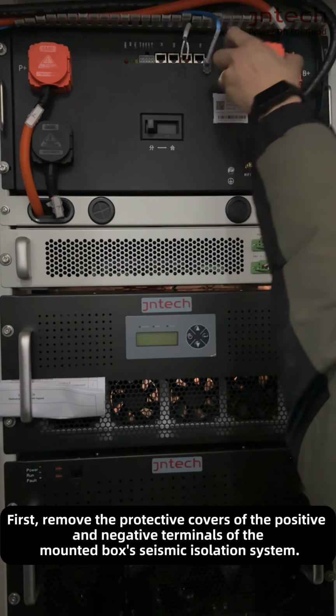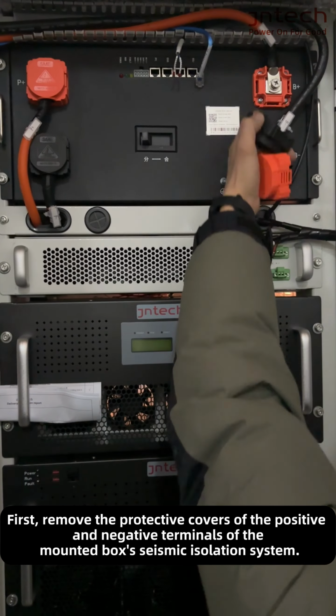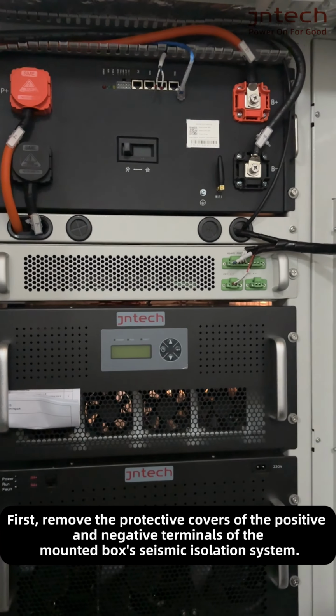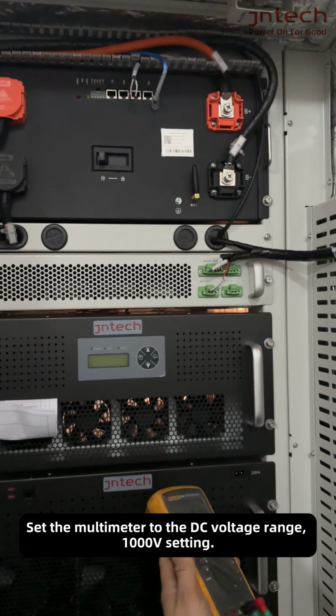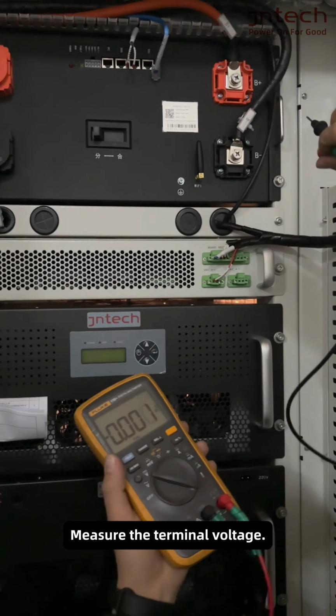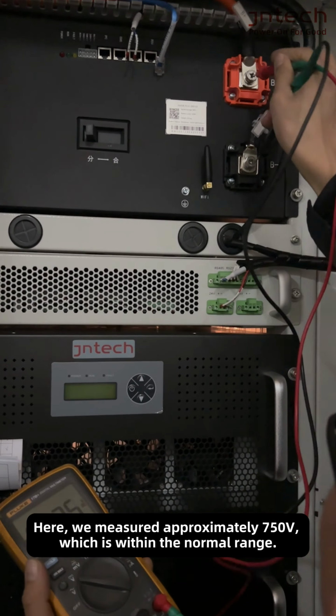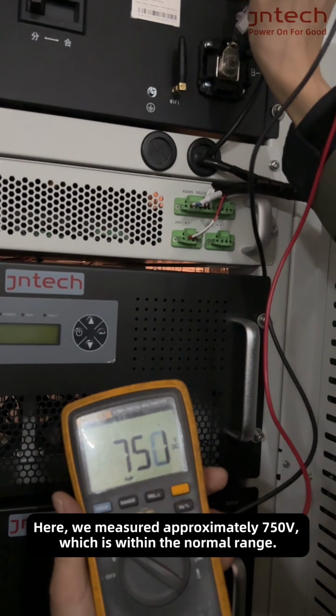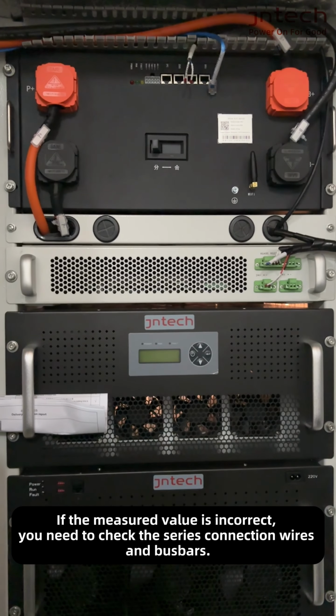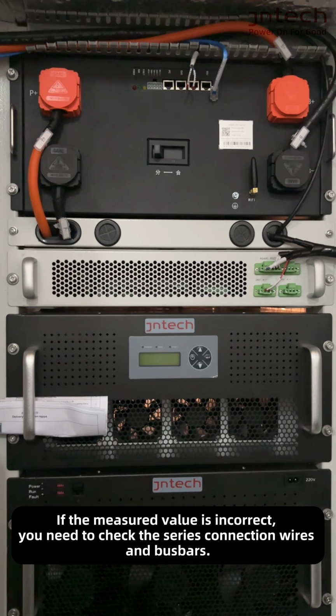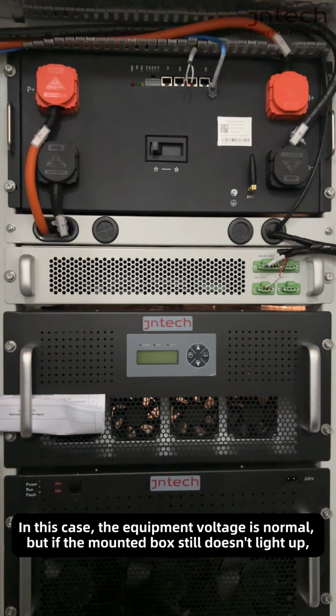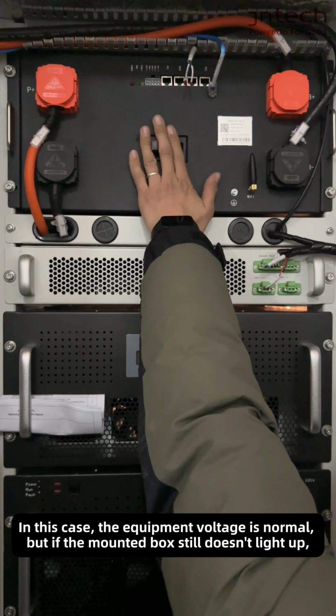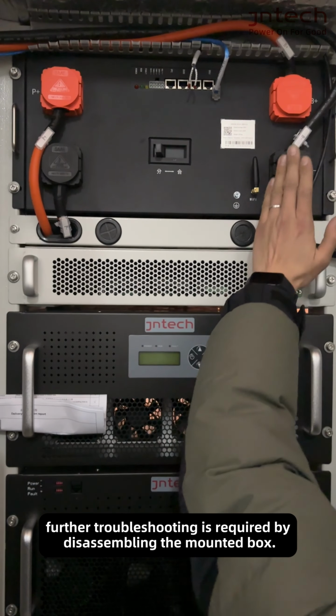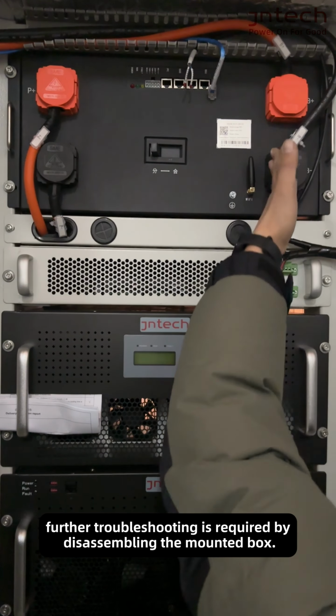First, remove the protective covers of the positive and negative terminals of the mounted box's seismic isolation system. Set the multimeter to the DC voltage range, 1000 volts setting. Measure the terminal voltage. Here, we measured approximately 750 volts, which is within the normal range. If the measured value is incorrect, you need to check the series connection wires and bus bars. In this case, the equipment voltage is normal, but if the mounted box still doesn't light up, further troubleshooting is required by disassembling the mounted box.